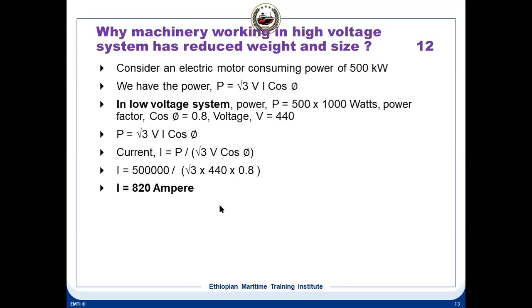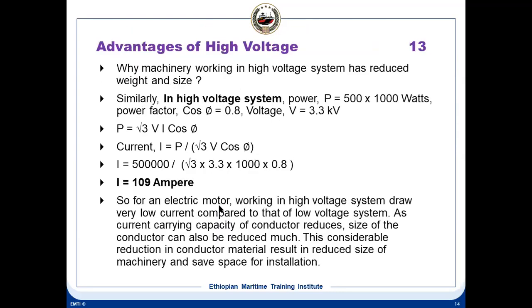Now here, why does machinery size reduce with the stepping up of the voltage? Suppose an electric motor is consuming 500 kilowatt of power. The power is √3 VI cos phi. If you use a 440 volt system, the current is going to be 820 amps, because I is equal to 500 kilowatt divided by √3 V into cos phi. So it becomes 820 amps at 440 volt. For the same motor, if you increase the voltage to 3.3 kV, then what happens? The current is calculated with P equal to √3 VI cos phi, using √3 into 3.3 into 1000 into 0.8. The current drastically reduces to 109 amps.